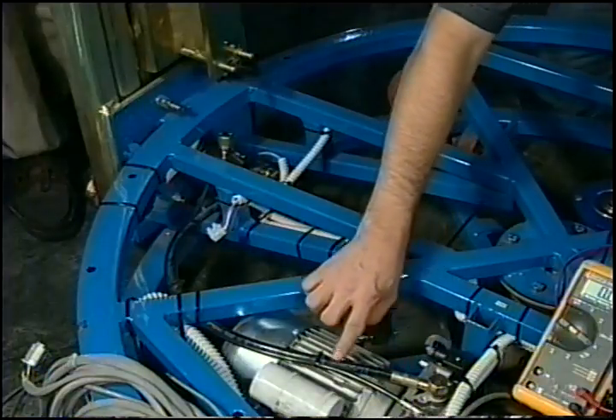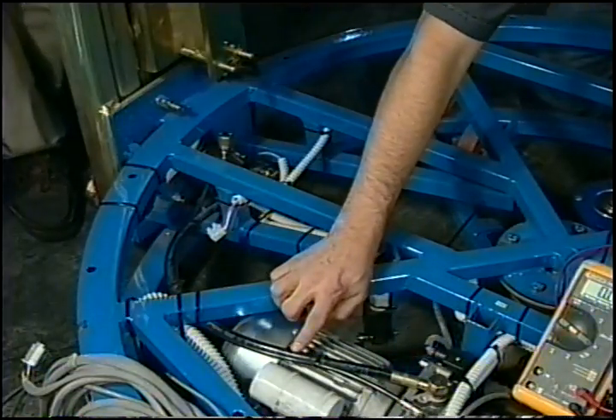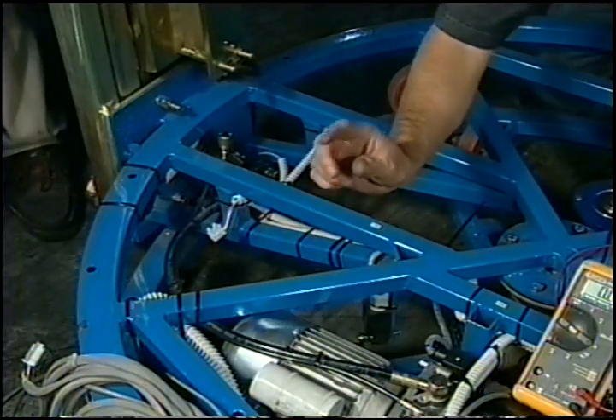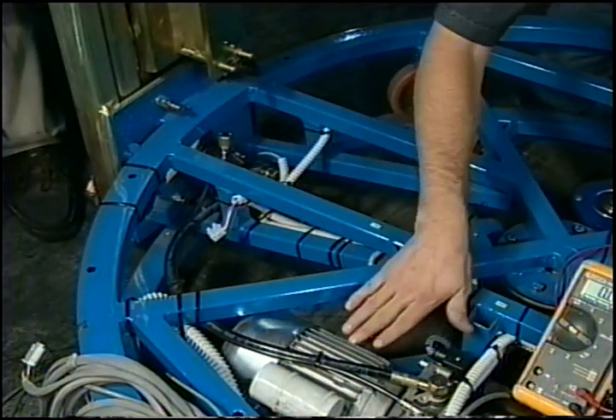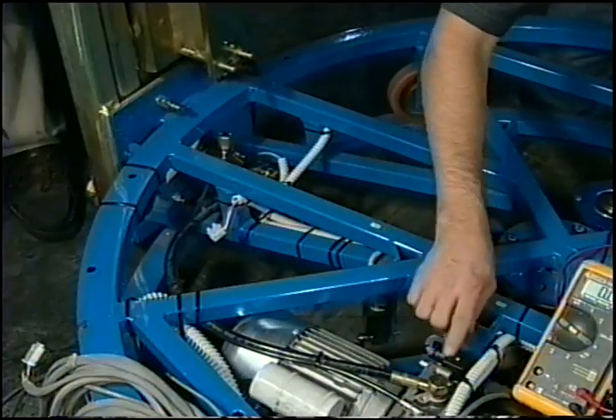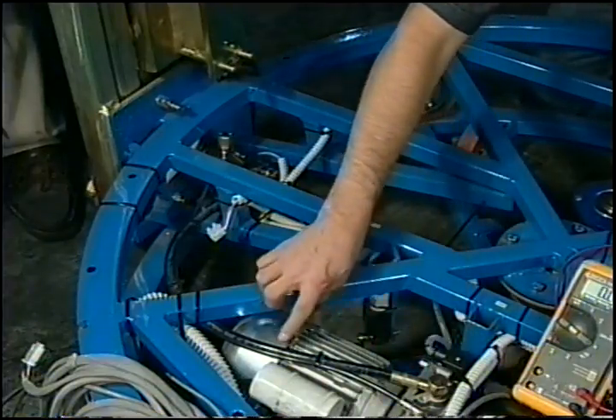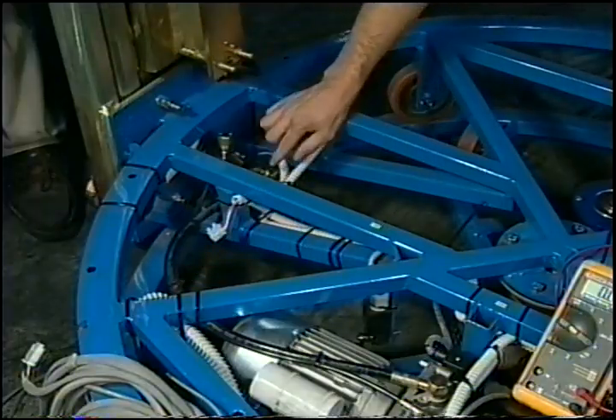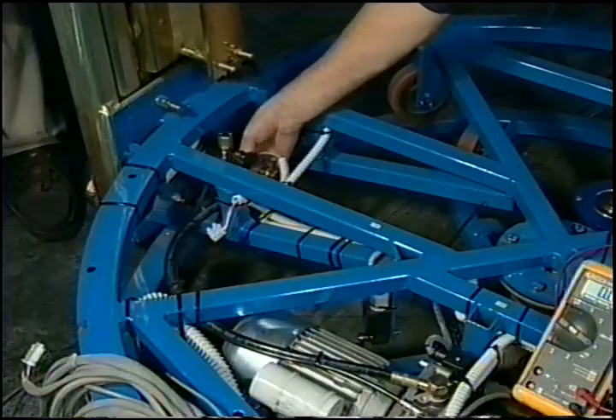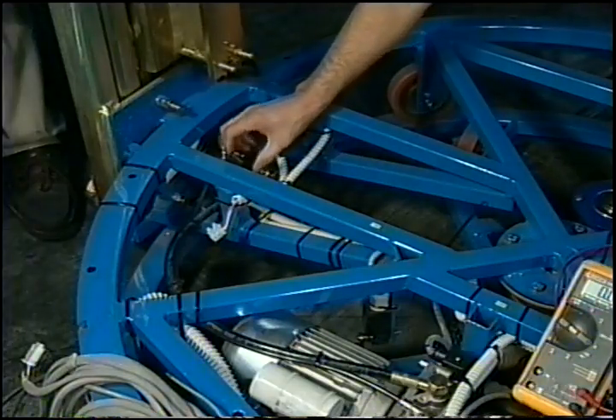Your valve itself still could be bad, but generally when this fails, it's going to be your coil more so than the valve. The larger of the two lines, the pressure line: when you point up your ride and J3 clicks in, or the relay at J3 clicks in and sends 120 to your pump motor, your pump's going to start. It's going to send pressure on the larger of the two lines. It's going to go directly to your 110 valve, and that's this valve here.